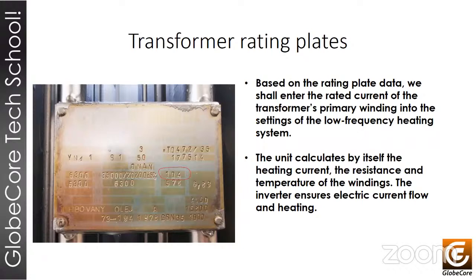Based on the rating plate data, we shall enter the rated current of the transformer's primary winding into the settings of the low-frequency heating system. We shall specify in the settings whether the transformer is with or without oil. We shall set the process frequency, normally 1 Hertz, and the drying process time in hours. The unit calculates by itself the heating current, the resistance, and temperature of the windings. The inverter ensures electric current flow and heating.